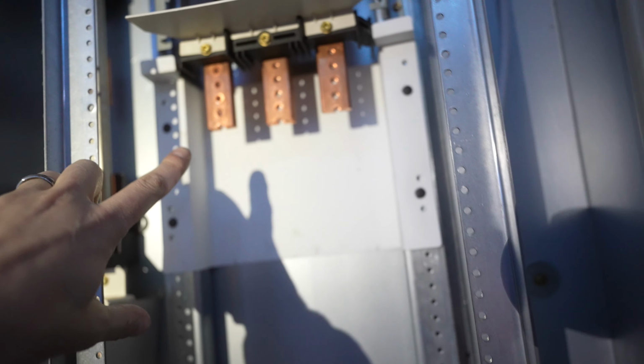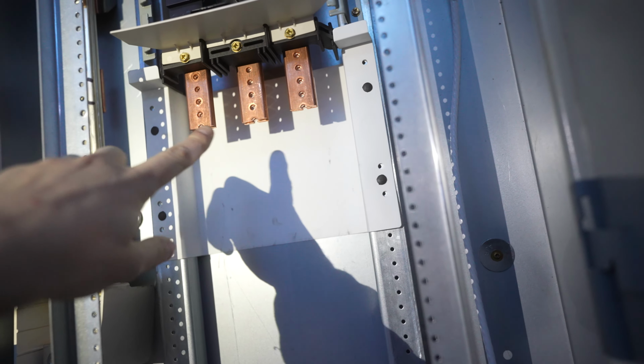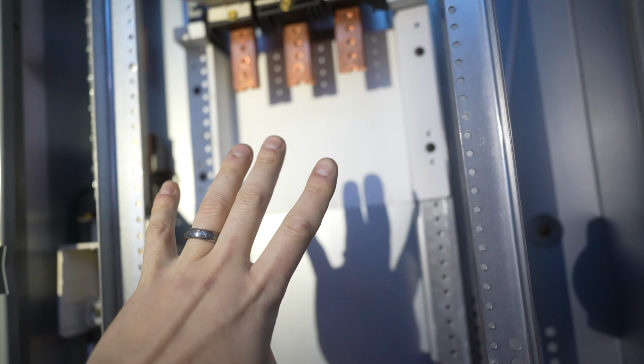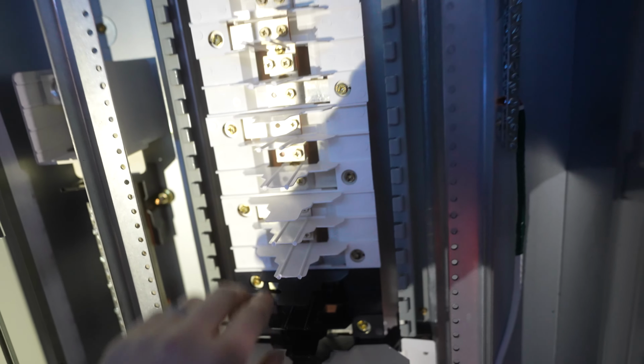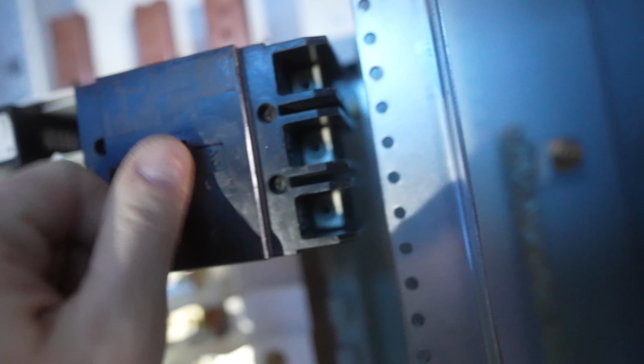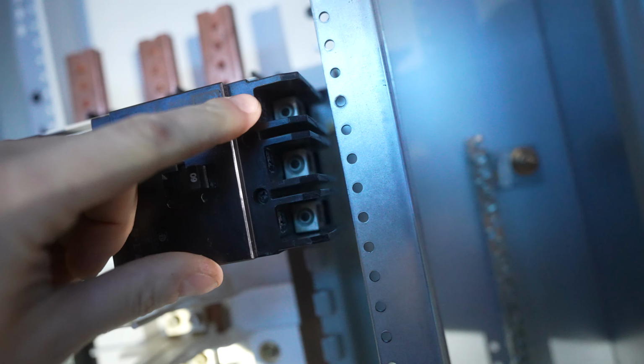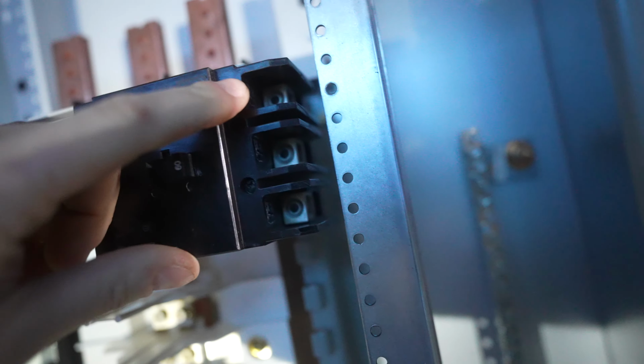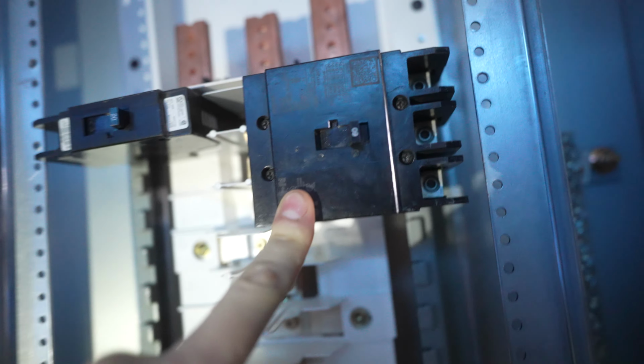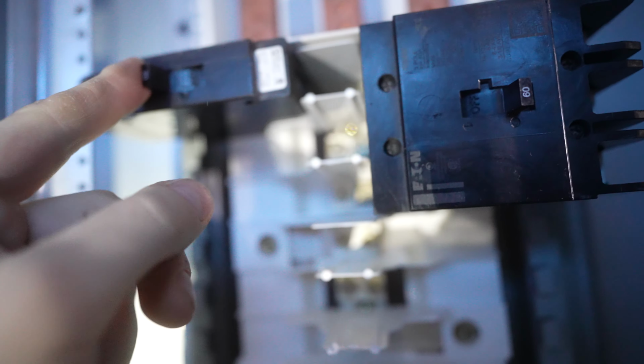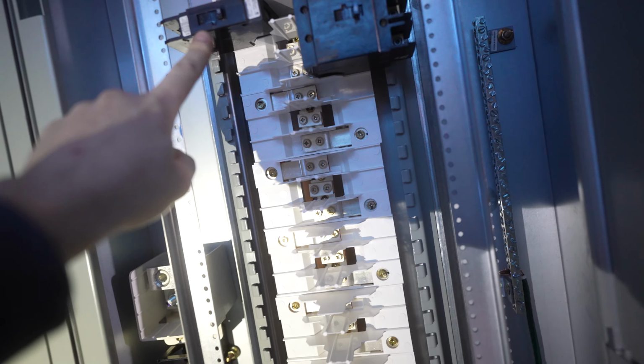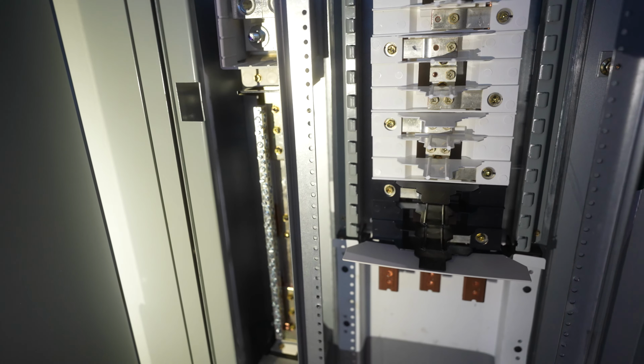Then we have a breaker that's going to be set right here. They have a special set you buy online that'll connect it to our bus bars here. And that breaker's a 400 amp breaker. It's going to power all of this, and then we're going to be running 60 amp. Here's one of the breakers here. This is a 60 amp breaker. Each phase is 240, 240, 240, 240 at 60 amps. It's a lot of watts. It's going to be loaded onto this breaker right here. Special breaker. And then we also have a single leg breaker. It's 20 amp. This will allow us to plug in our lights and run other things. The only problem is you have to buy everything at 240. Since our single legs are all 240, our lighting system in the container is also going to be 240.